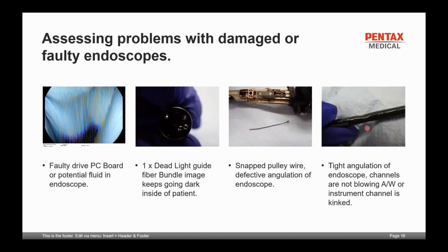Okay, if at any stage the endoscopist is complaining of a tight segment stay core, or the tip deflection or the tip angulation of the endoscope is feeling tight, please have a look at the externals of the endoscope. Make sure that there's no crush marks or damage marks to it. If there is, that could definitely hamper the angulation of the endoscope. And again, the air, water, and instrument channels may become damaged as well from that type of damage to the endoscope.